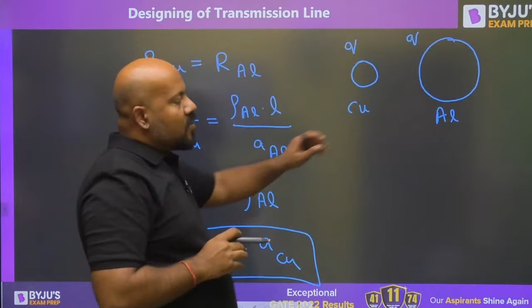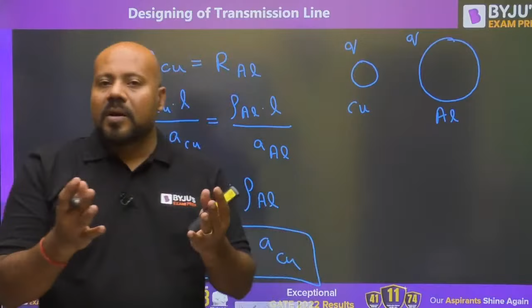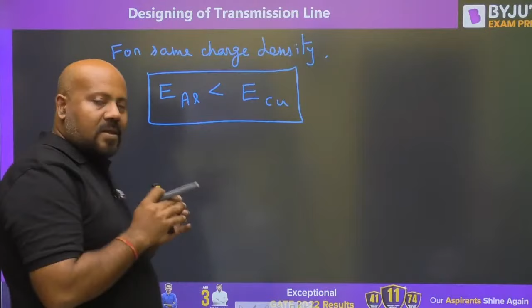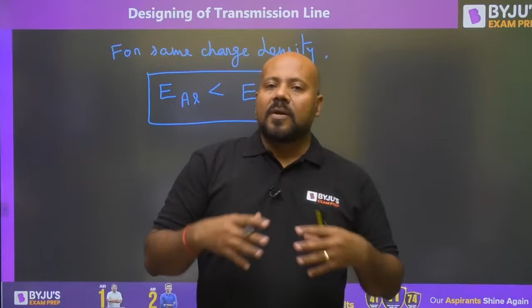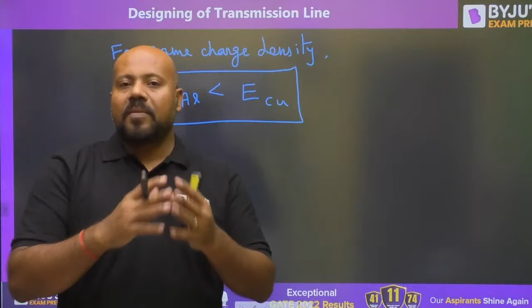Because your aluminum conductor has a larger cross-sectional area, or more diameter and radius, the electric field stress at the surface of the conductor is going to be less in case of aluminum compared to copper. This electric field intensity is a very important parameter for designing our transmission line, because at a very high voltage level, electric field stress gives you the nature or intensity of corona, which is an important loss in the transmission line.